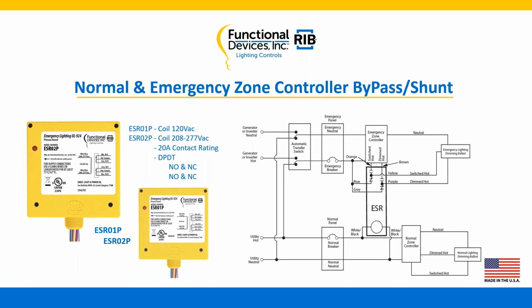You'll notice the nomenclature over here: our ESR 01P, coil voltage on that is 120. The ESR 02P, our coil voltage is 208 through 277. So we've got the standard voltages used in the lighting world for sure. 20 amp contact ratings on these. The important piece is this is a double pole, double throw, so there are two sets of normally open, normally closed contacts there.